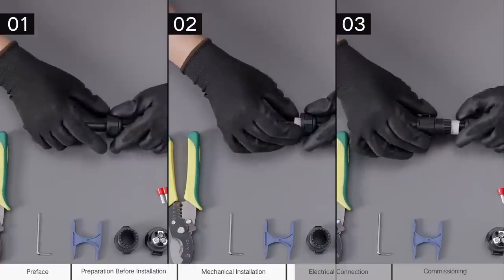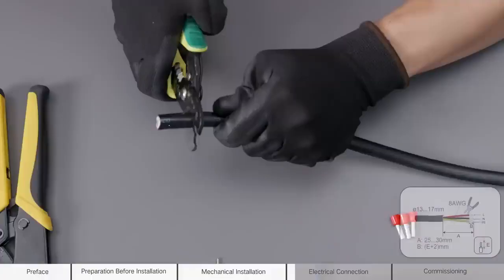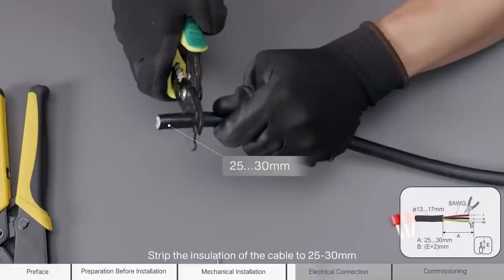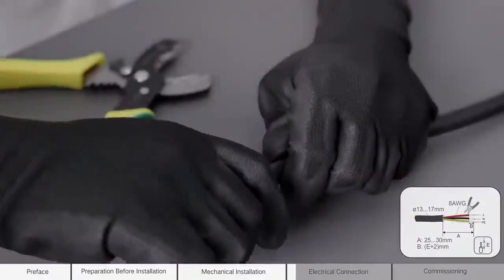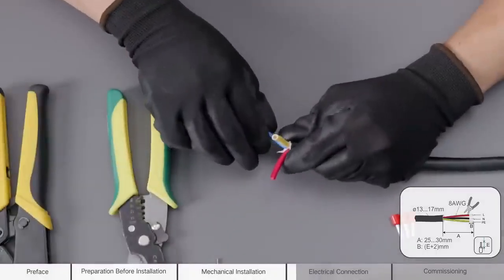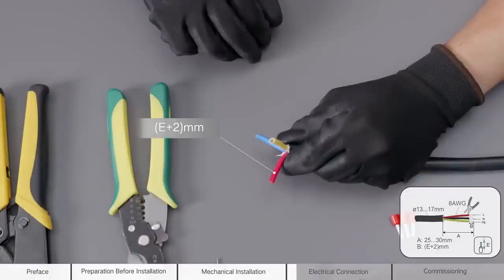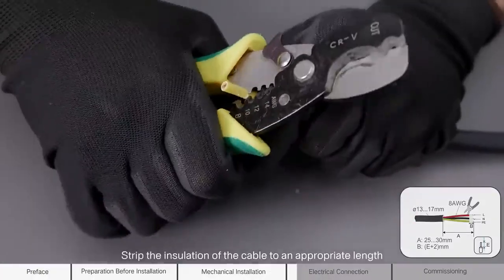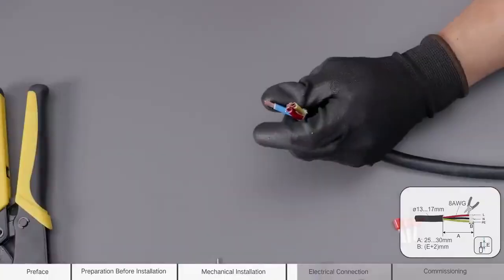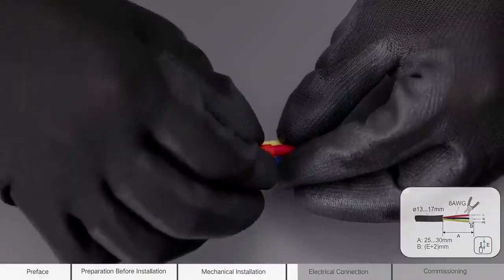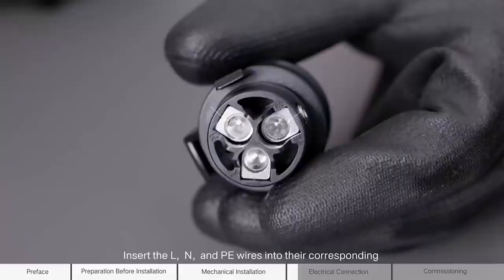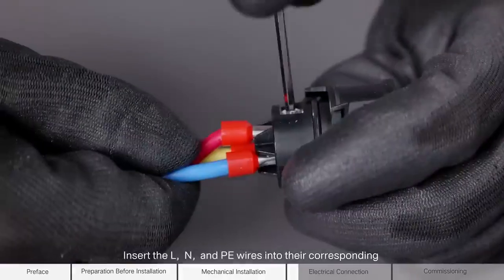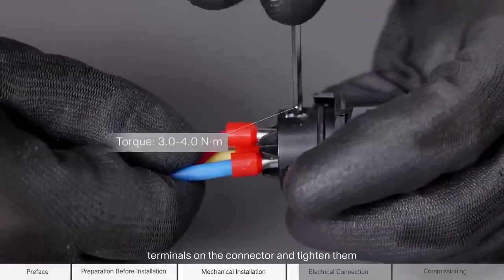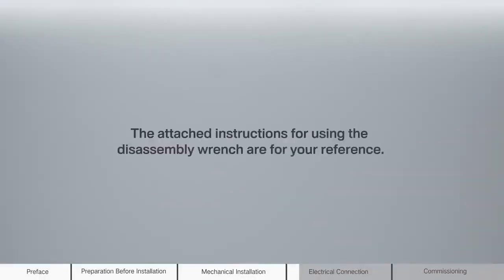Route the AC cable through the connector. Strip the insulation of the cable to 25 to 30 mm. Strip the insulation of the cable to an appropriate length. Crimp the terminals. Insert the L, N, and PE wires into their corresponding terminals on the connector and tighten them. The attached instructions for using the disassembly wrench are for your reference.